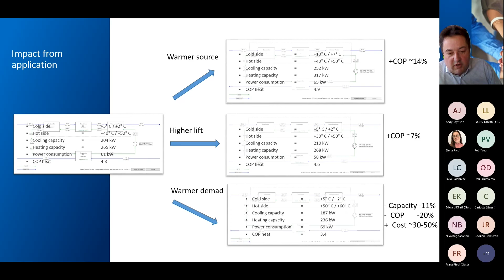Another thing also, had we chosen 60 instead of 50 in inlet temperature, we would have reduced the capacity of the machine by 10%, meaning the customer had to buy a more expensive machine. And lastly, every compressor is associated with a lift, and when you move to a higher lift, you also have greater demands for your compressor. In this case, it would have meant going up to a compressor that would have required another set of bearings, meaning it would have gone up to what we call a 40 bar machine instead of a 28.